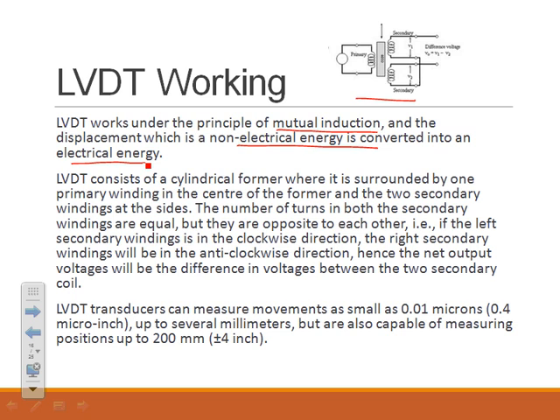LVDT is a cylindrical former surrounded by one primary winding at the center, and two secondary windings on either side. There is a primary winding, then two secondary windings, represented by S1 and S2.